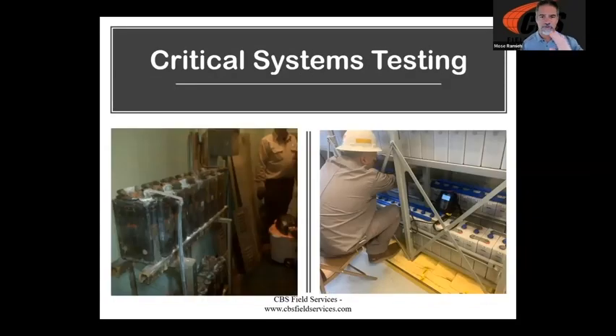All right, battery systems. Once again, another crucial item. That's another reason that light might be out on your breaker, but if your battery system isn't working, you're not going to have that critical protection that you need. Most battery systems don't look this bad. We did have a customer here twice recently, two different customers, that by all accounts, their battery system looked fine, and the charger was maintaining what looked like proper voltage, but when they went to operate equipment, the charger wasn't capable of providing enough current, right? So the battery system was damaged, and it was also not able to provide enough current. So instead of a breaker properly charging and being able to be closed, it presented itself as a breaker issue and what turned out to be a control power issue. So once again, check on your battery systems, maintain those as well.